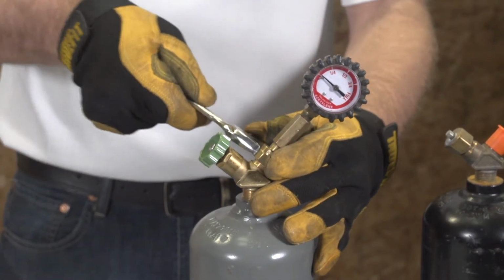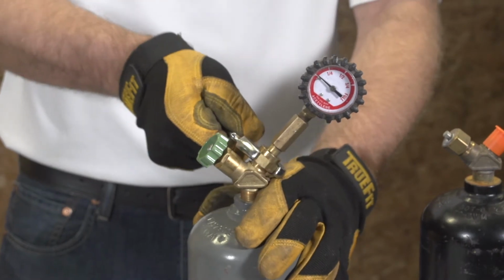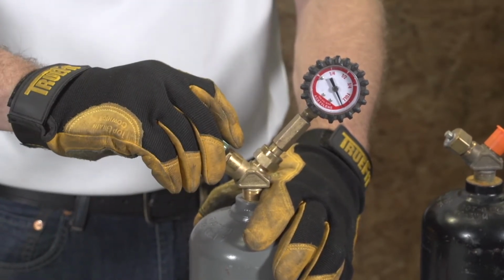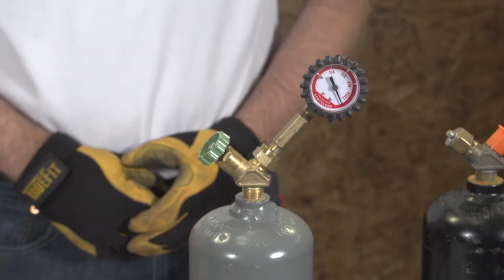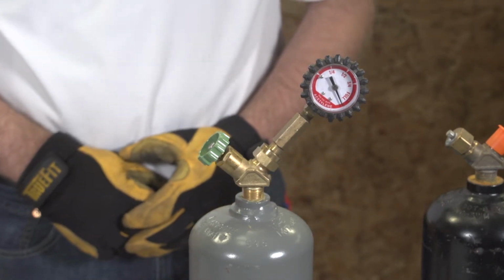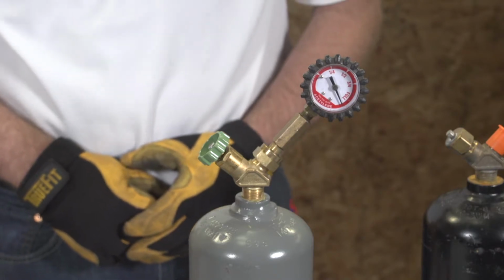What this means for you is that if it's cold outside, the liquid in the cylinder will be cold as well, causing the pressure rating to show a lower level of acetylene. As the cylinder warms up as it is being used in the field, the liquid will also warm and the regulator will begin to show the true level of contents in the cylinder. Due to this extreme variability, the inlet pressure rating of these cylinders is not a good indicator of contents level.